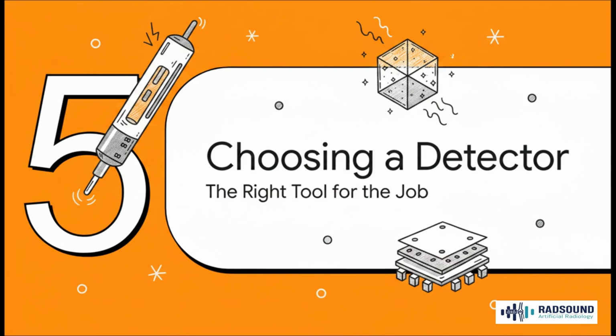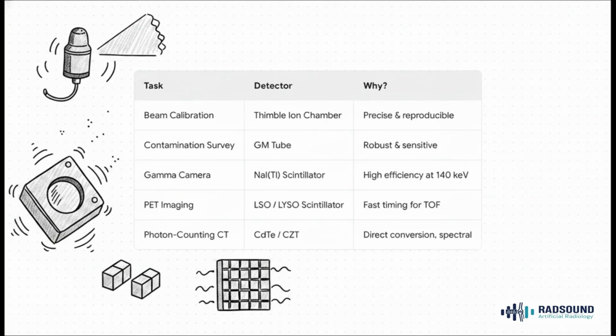Okay, so we've met the whole gang of gadgets. We've got the gas detectors, the scintillators, and the semiconductors. So now let's put it all together and figure out which one you would actually grab for some common clinical tasks. Think of this as your clinical cheat sheet. Need to calibrate a beam? You have to use a thimble ionization chamber for its precision and reproducibility. See a spill and need to check for contamination? You grab that GM tube for its sensitivity and that helpful audible click. Doing standard nuclear medicine imaging, the great light output and high efficiency of NaI(Tl) is your go-to. For a modern PET scanner, it's all about the fast timing of LSO for time of flight. And for that cutting-edge spectral CT, it's the direct conversion of CZT that makes it all happen.